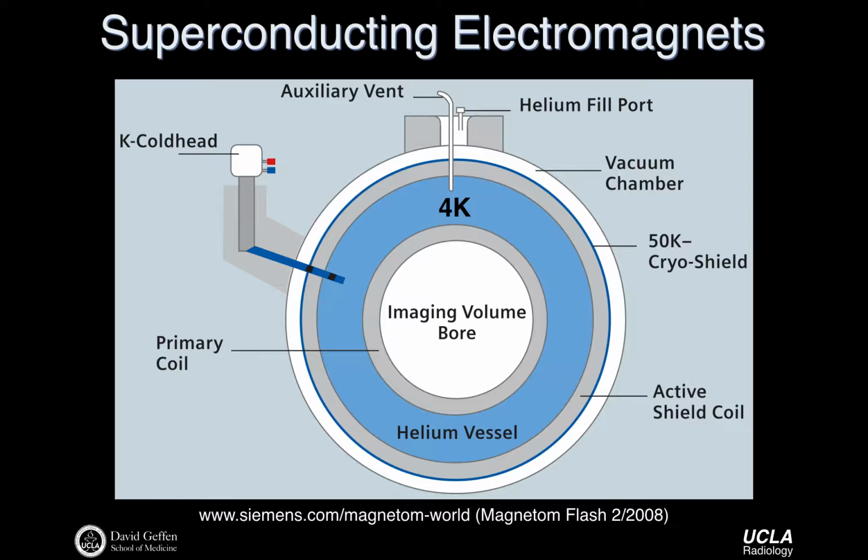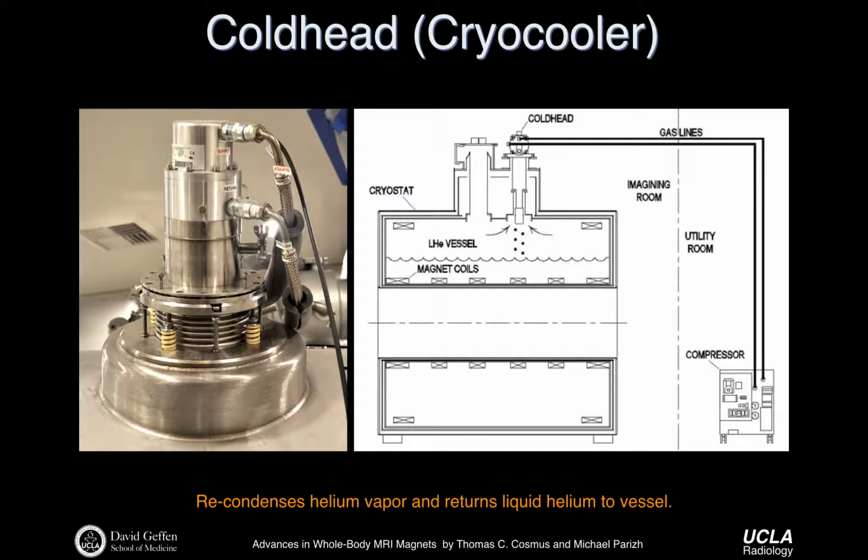There's a couple of hardware elements here that give us access to, in this case, being able to refill the helium. The helium will boil off slowly, and we do at times have to replace it. And then there's a cold head for recompressing helium as well. We'll talk about the design just a little bit more in the next couple of slides. So I won't spend too much time on this. This is what's called the cold head.